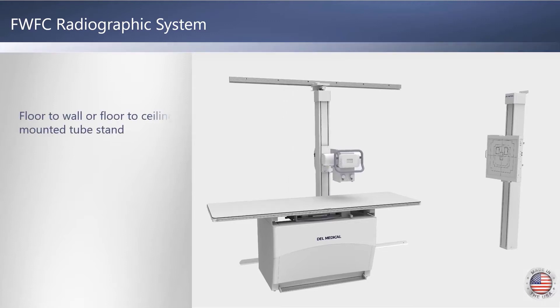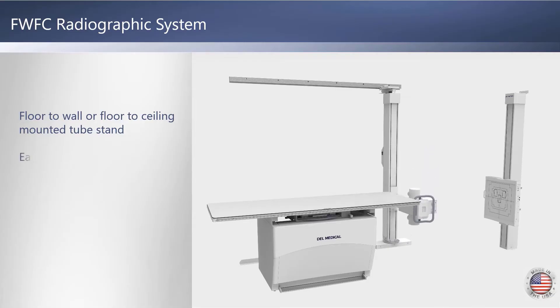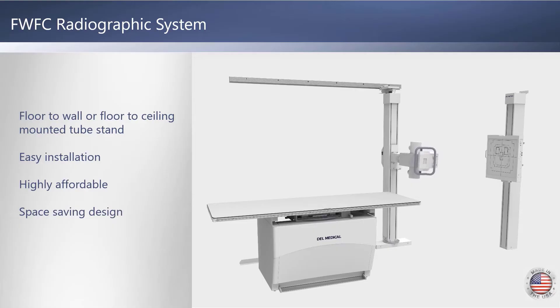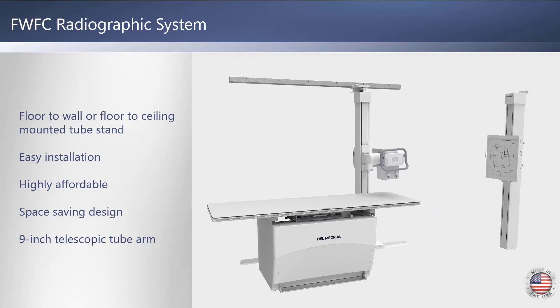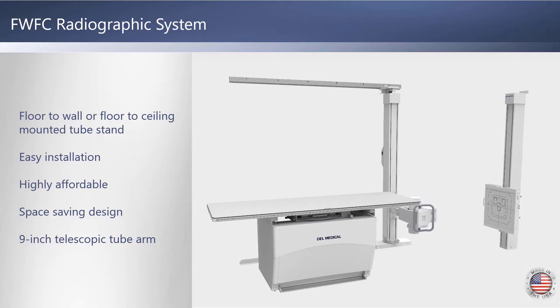The FWFC is named for its flexible tube mounting options. The tube column is mounted to tracks securely installed on the floor and wall or floor and ceiling. It's the most affordable Del Medical Radiographic x-ray system available, but the FWFC makes no compromise in quality or functionality. The space-saving design allows for installations in the smallest of rooms, and the nine-inch telescopic tube arm and four-way table float provide extensive imaging range.